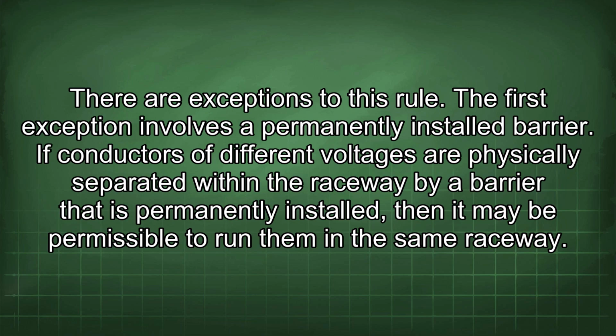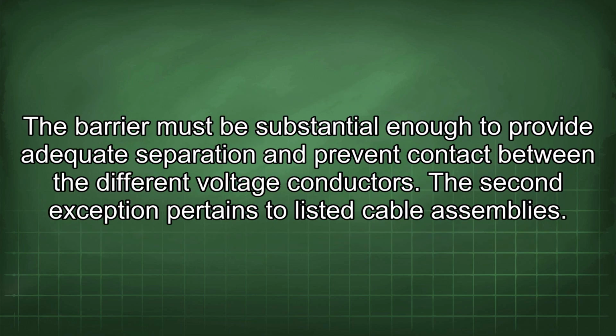The first exception involves a permanently installed barrier. If conductors of different voltages are physically separated within the raceway by a barrier that is permanently installed, then it may be permissible to run them in the same raceway. The barrier must be substantial enough to provide adequate separation and prevent contact between the different voltage conductors.